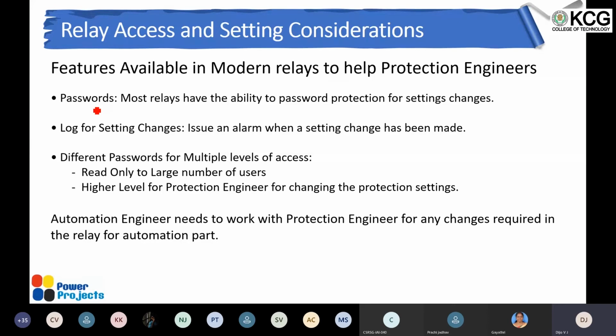And another option is a login log for setting changes. So when there is a setting change, we can set the relay to give an alarm to the substation control and monitoring system, so that the protection engineer knows that there have been some changes here. He will have his own logs for checking when he has changed the settings. So if it is not matching with that, then he can straight away go into the relay and see if there is an issue in the settings. So that is one thing. And the passwords for multiple levels of access: one is a read-only option, which may be given to a large number of users, but a higher level for the protection engineer for changing the protection settings.